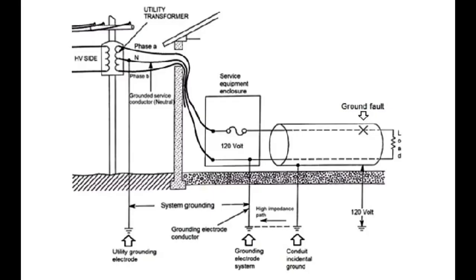It's not allowed to do it because in North America you have the transformer maybe 20 feet from your house, but for me the transformer is usually 2 miles far away from the house, and there is no conductor with zero resistance, so there will be some voltage on the neutral. When you measure between neutral and grounding, you will find there is some voltage. If you have 2 miles, it can be up to 20 volts.